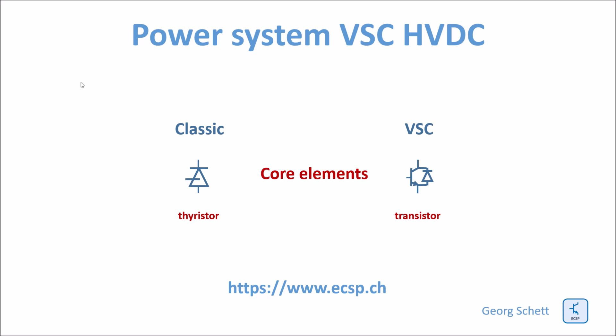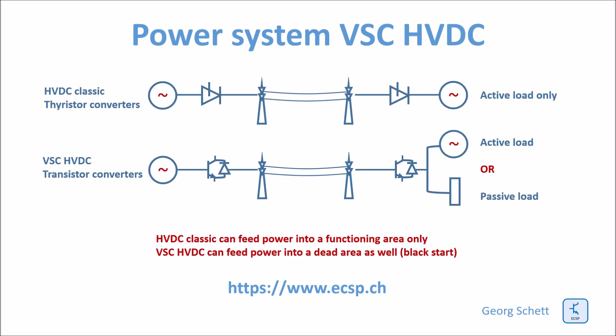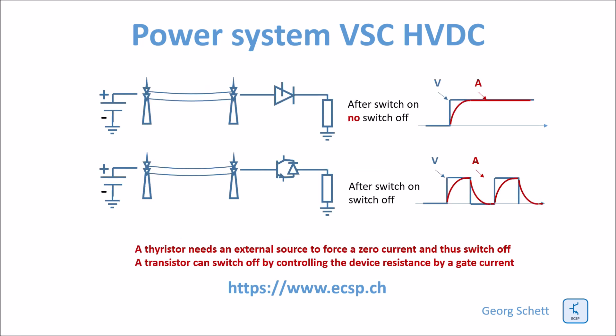The transistor used here is called an IGBT. HVDC Classic can feed power only into an active AC network, whereas VSC HVDC with transistor converters can feed into both an active network and a passive network. The key difference lies in the inverter — the part which rebuilds an AC from a DC source. The DC source, remember, is the line.